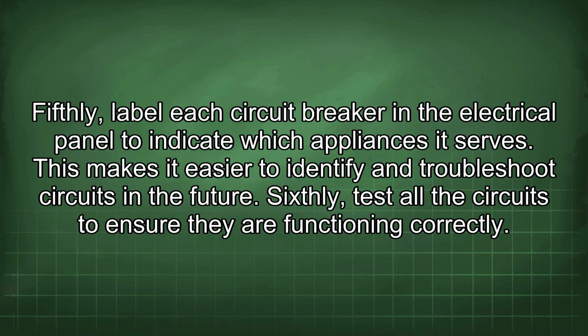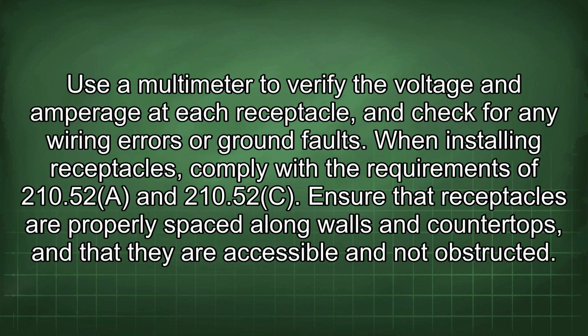Sixthly, test all the circuits to ensure they're functioning correctly. Use a multimeter to verify the voltage and amperage at each receptacle and check for any wiring errors or ground faults. When installing receptacles, comply with the requirements of 210.52(A) and 210.52(C). Ensure that receptacles are properly spaced along walls and countertops, and that they are accessible and not obstructed.